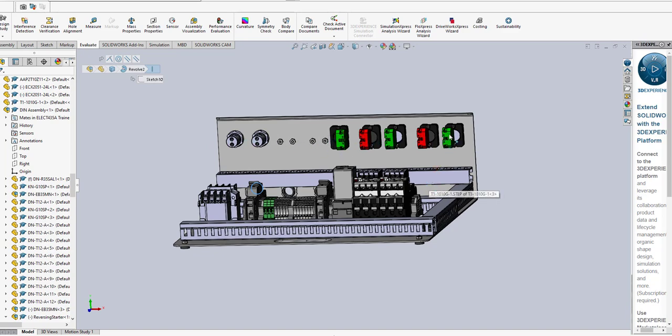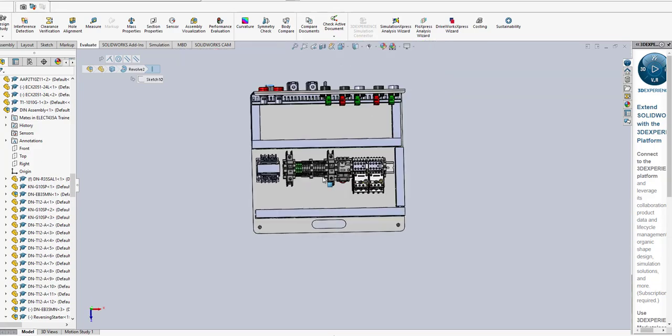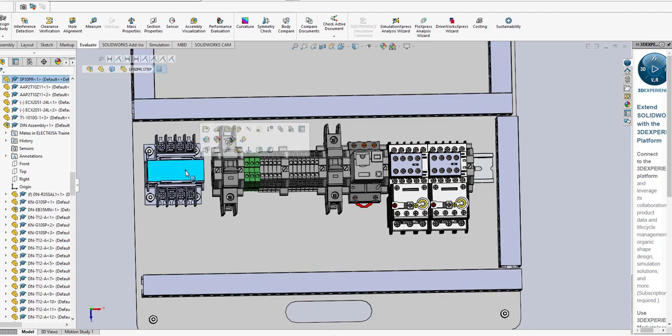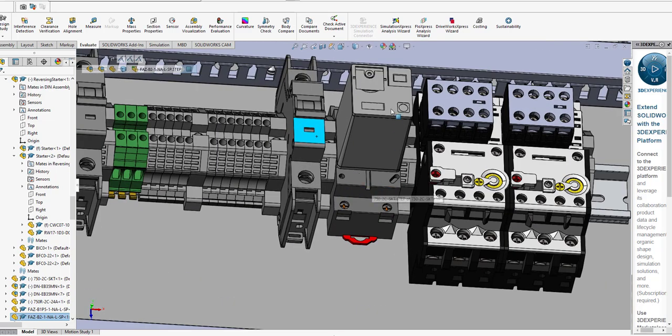And then you'll wire and come down in the cable trays and run the wires around the cable trays and connect up to this main area of components. Have a transformer to go from the 120 volts to 24 volts. 120 volt circuit breaker, 24 volt circuit breaker for the control transformer. We have a control relay here and its socket. You'll be wiring that up.